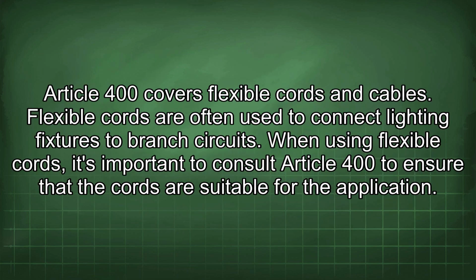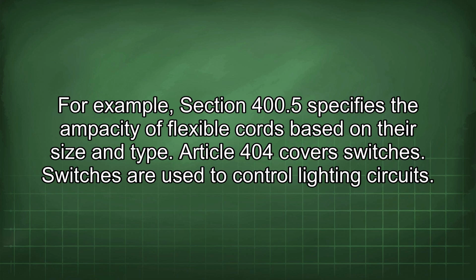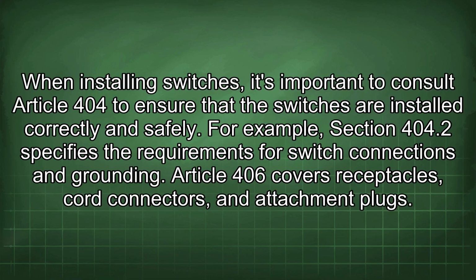Article 400 covers flexible cords and cables. Flexible cords are often used to connect lighting fixtures to branch circuits. When using flexible cords, it's important to consult Article 400 to ensure that the cords are suitable for the application. For example, Section 400.5 specifies the ampacity of flexible cords based on their size and type. Article 404 covers switches. Switches are used to control lighting circuits. When installing switches, it's important to consult Article 404 to ensure that the switches are installed correctly and safely. For example, Section 404.2 specifies the requirements for switch connections and grounding.